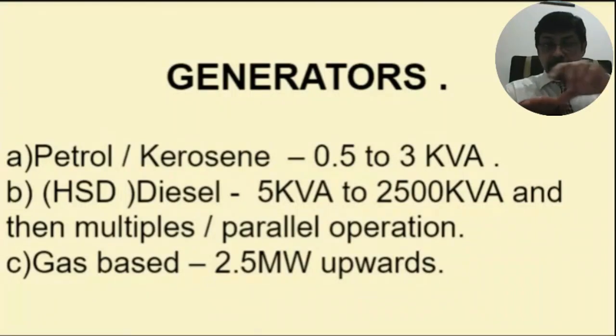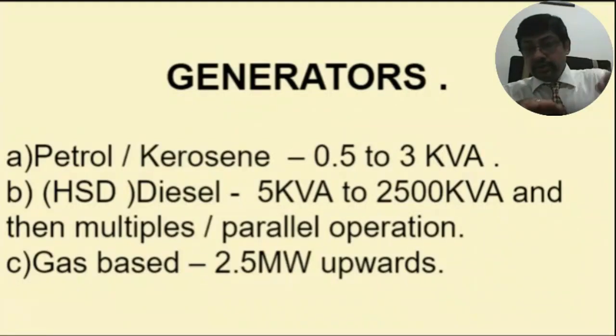Suppose the bus bar load is approximately say 2500 kVA. So 1500 is taken care of by one. The second will come and there will be a load sharing in equal proportion. It will not be 1500 and the next 800 or 900 on the other. No, it's going to be 2400 is the grid load, bus bar load, and that load is going to be distributed amongst these two generators equally. So that is known as proper load sharing in parallel operation.